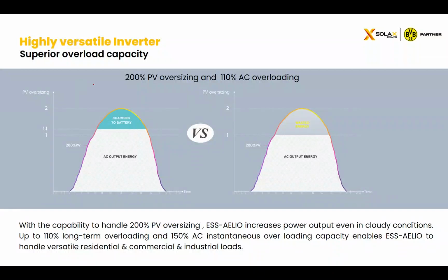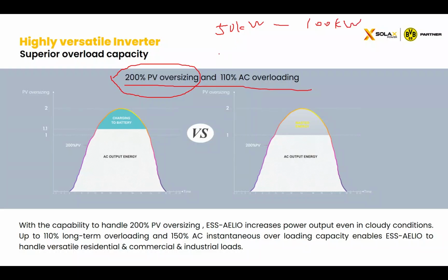Also, 200% PV oversizing and 110% AC overloading. 200% PV oversizing means if you buy a 50 kilowatt AELIO, you can connect 100 kilowatts of PV system with it. When the PV panels supply 100 kilowatts to the AELIO system, 50 kilowatts will be used to charge the battery, and another 50 kilowatts will be used to supply the loads. So although the system you buy is a 50 kilowatt system, it would actually perform like you bought a 100 kilowatt system.